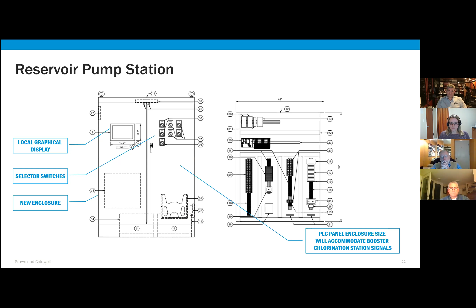So there are variable frequency drives at the reservoir that control the booster pumps at the reservoir site. Another thing that our project will be doing is upgrading these from hardwired to network communication between the existing VFDs and the new control panel. So this will allow for pump control and transfer of additional monitoring all over a single cable. And these are Siemens VFDs, and the PLC is a Siemens PLC, so they'll talk very well together.